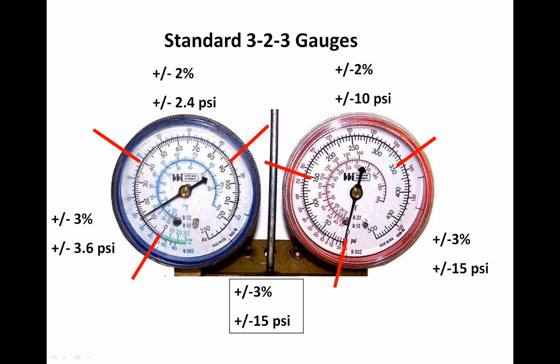A standard gauge, when you look from 0 all the way up here, if we follow this up to this point right here, okay? So from 0 to 40, that gauge is plus or minus 3%, and that equates to 3.6 psi. So it's plus or minus 3.6 psi, all right? When we get to the center of the span of the gauge, and this is where the gauge is most accurate, so now we're up here at the top here, and that becomes plus or minus 2.4 psi. And then the latter half of the gauge from 90 to 120, which is actually right here where that's going to stop. Again, we're at plus or minus 3.6 psi.